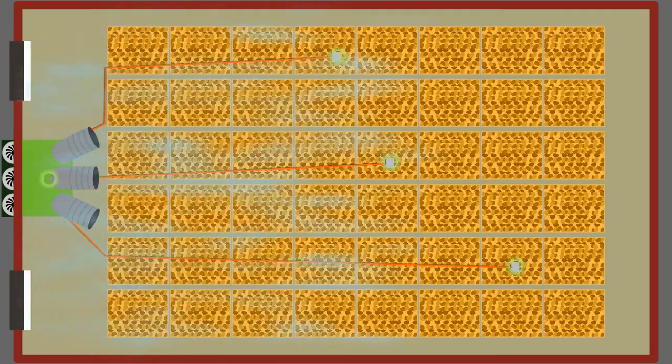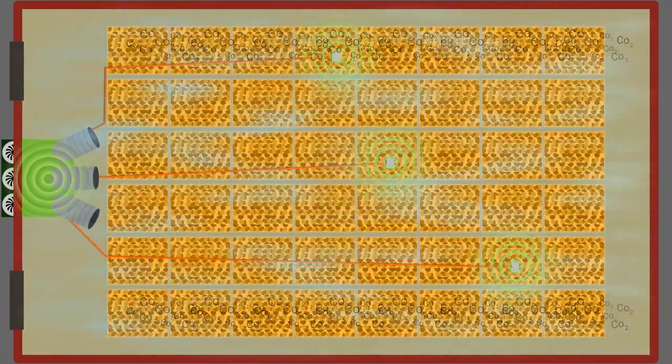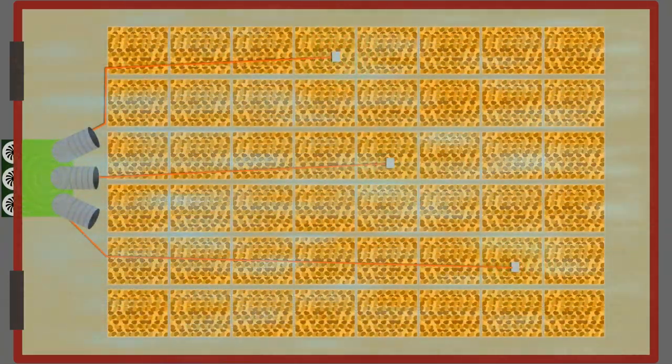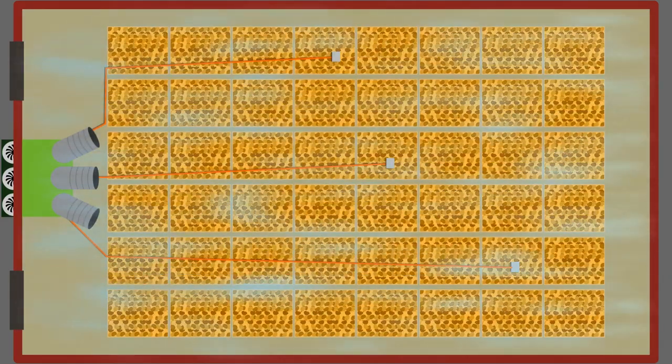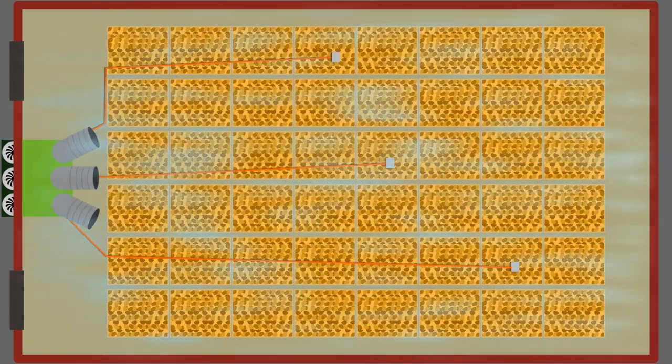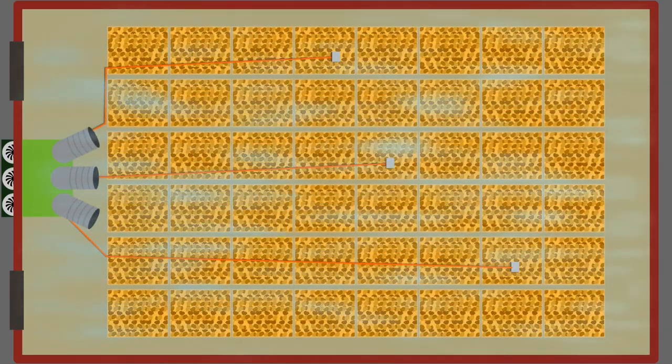The potato is slowly cooled down. The potato produces carbon dioxide which is measured. The Vision Control then ensures that the potatoes get enough fresh air to limit the carbon dioxide content. A high level of carbon dioxide results in accumulation of sugars in the potato, which affects the frying color during processing.